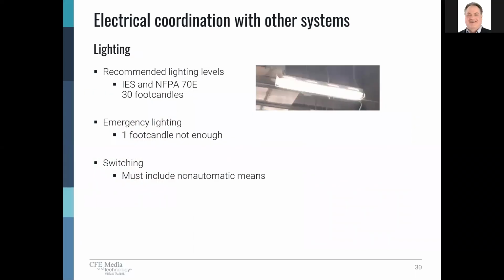Lighting is another key component of electrical room design. The lighting standards generally call for 30-foot candles in electrical rooms, which should be sufficient. However, when you're on emergency power or during an outage, you don't want to just do the typical 1 or less foot candles for egress and emergency access. Basically, good recommended practice is that all the lights in the main electrical room or key electrical room should be on emergency power. It's just simply not that big a cost, even if you don't have a generator, to add battery packs. Make sure the entire room is lit.